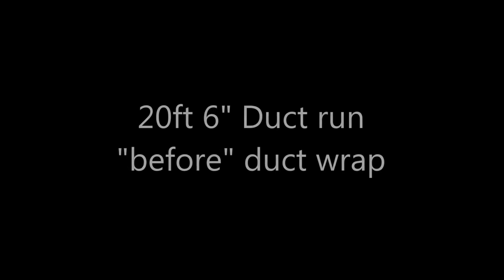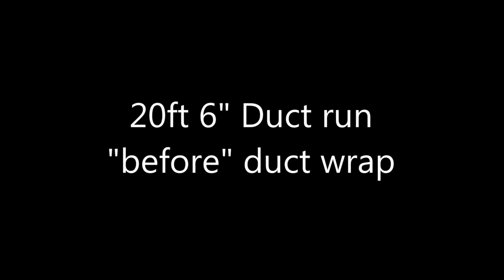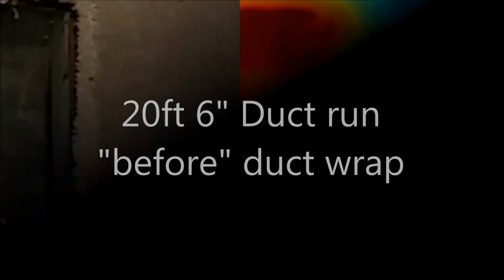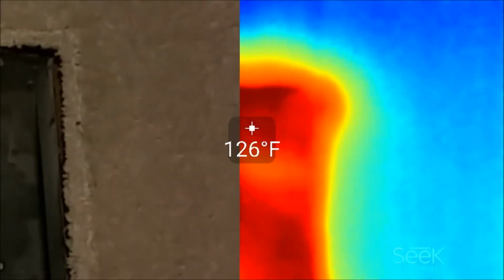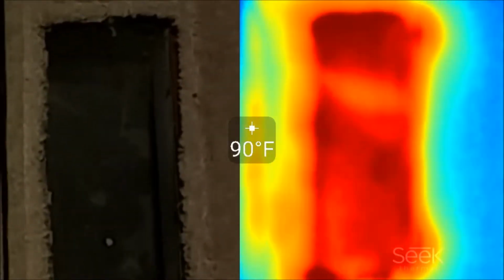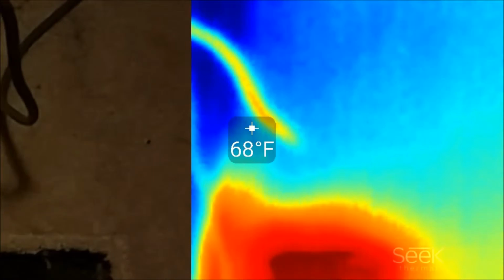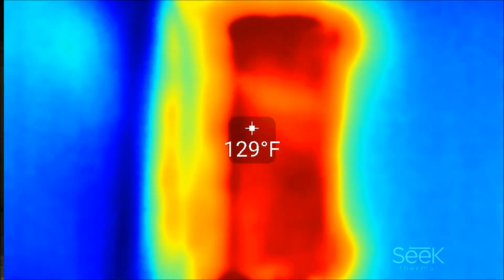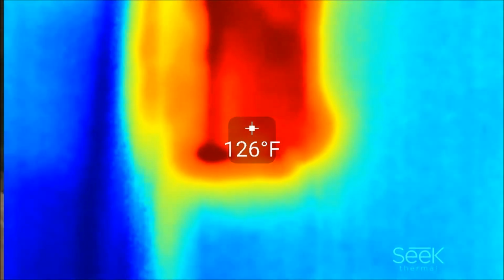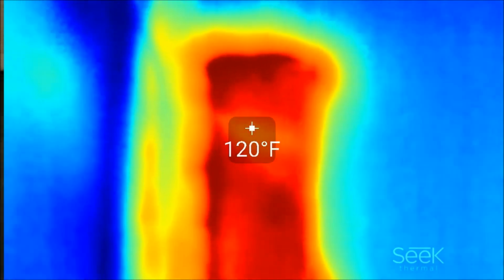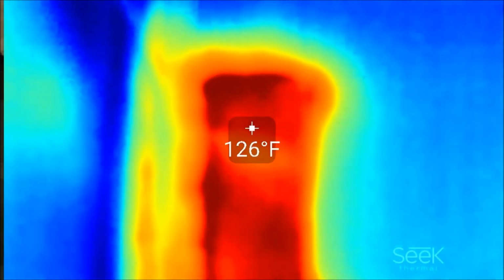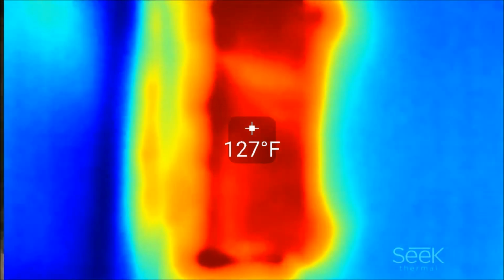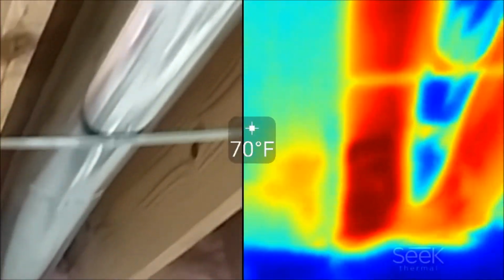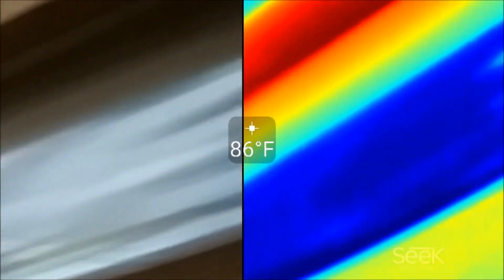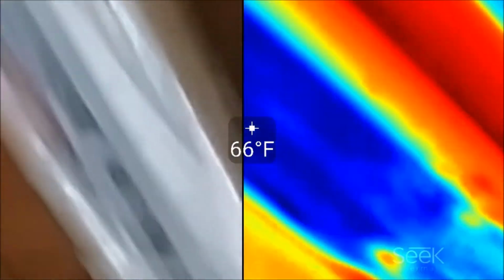Okay, here's a 20-foot section that I wrapped with a 6-inch duct wrap. This is the before snapshot from the thermal imager, with the register temp hovering right around, if this thing will stabilize out, about 127, 129 degrees coming out of the register. So that's not too bad. The next image is what it looks like underneath the register. This is in the basement, and you can see this cavity is really heating up.